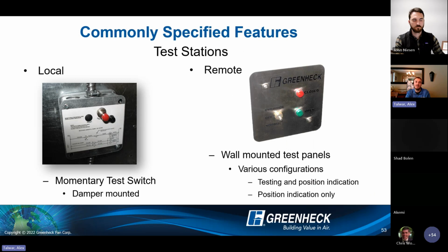Few options for test stations. So locally mounted, the momentary test switch, just really a cover on the outside of the junction box of the RRL or the closure device. It's got a little red button on it. Walk up or climb up, I suppose, and push the red button that cuts the power to the actuator. You can listen or watch or check that your damper is closing. When you release the button, it restores the power to the actuator, allows the damper to reopen again.